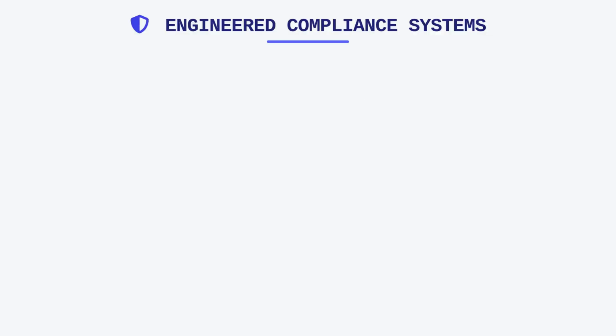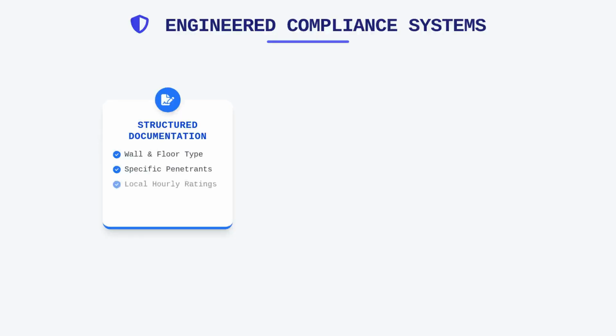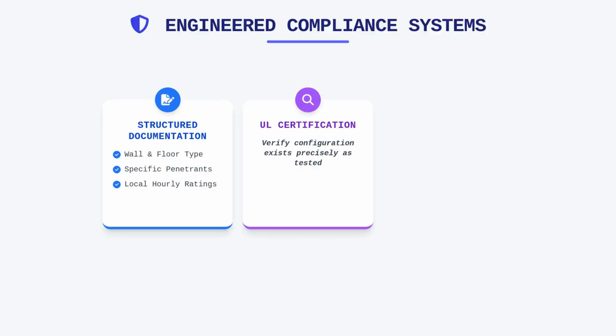Engineered systems provide a structured approach to documentation and compliance. By carefully documenting the wall or floor type, the specific penetrants, and the hourly rating required by local codes, we finalize the design in a way that is easily auditable by inspectors. This documentation must explicitly list the chosen UL system, certifying that the configuration exists precisely as tested. If a specific condition does not appear in the UL directory, one must seek an engineering judgment from the manufacturer, which provides a technical assessment based on existing test data.